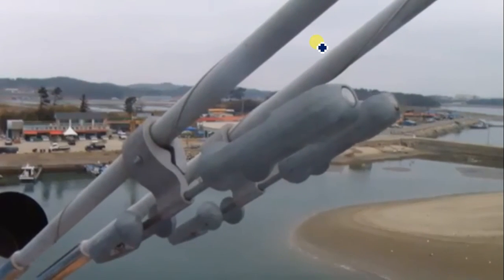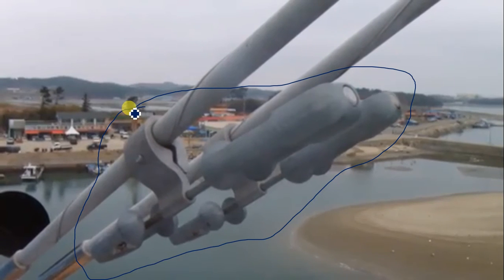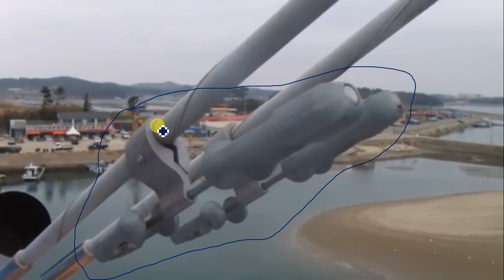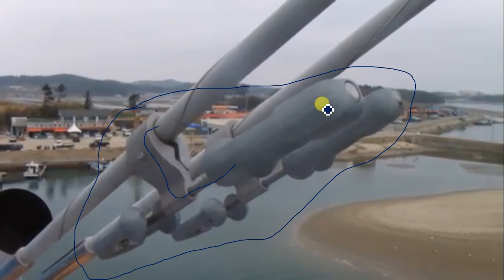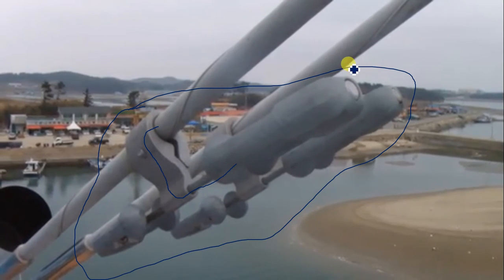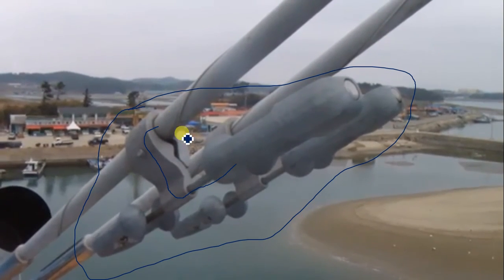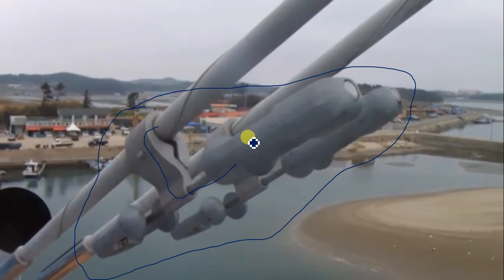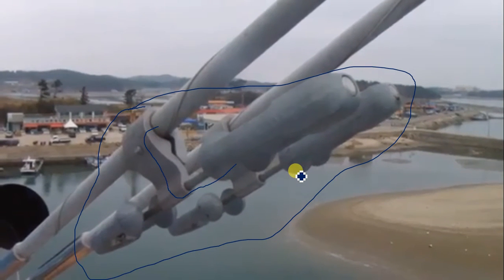So here you can see your conductor is moving, and at the same time these Stockbridge dampers are installed on your conductor. These vibrations are going to be converted into heat, and this heat is going to be passed through this clamp to these steel wires to these hollow weights, and that is why you can see there is less vibration in your conductor right now. So in such a way the Stockbridge damper is used to damp out the oscillations. Okay, so I hope you understand the working of the Stockbridge damper.